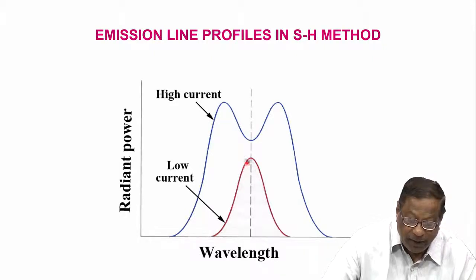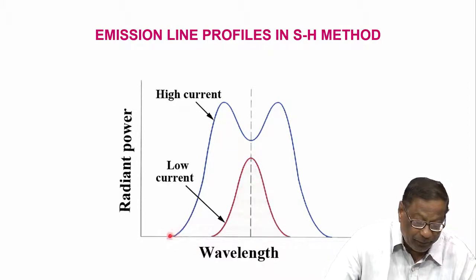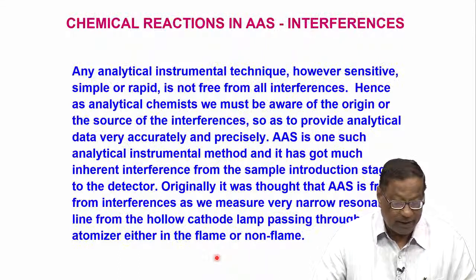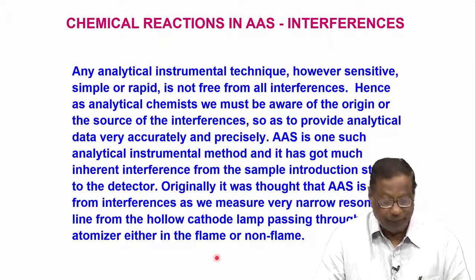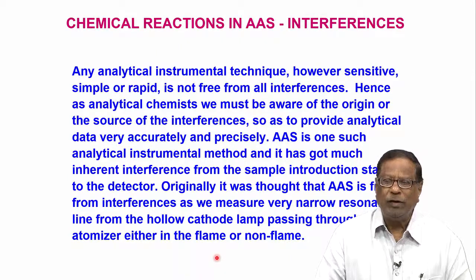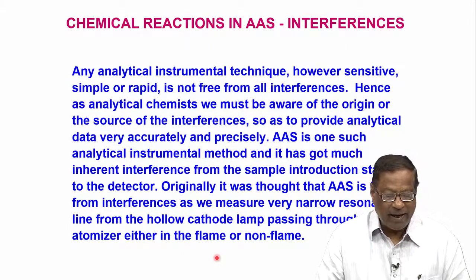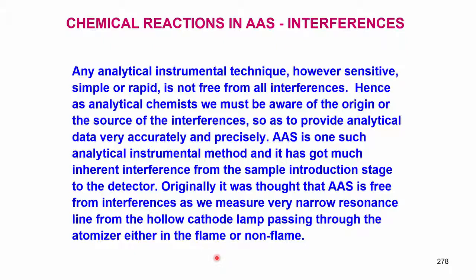At low current, I have atomic absorption, and at the high current level, there is reversal, and then only the atomic absorption difference is measured in the Smith-Hieftje correction. Okay. So, that is about atomic absorption background correction.